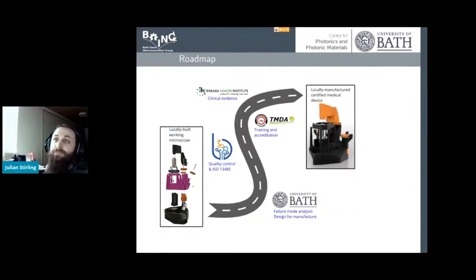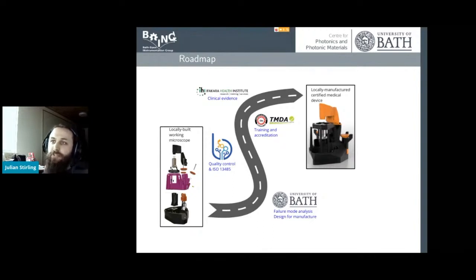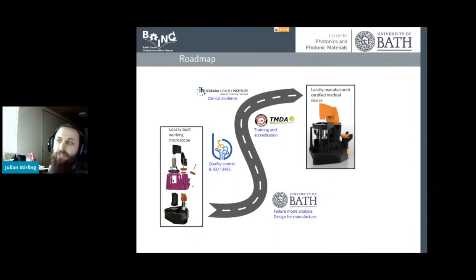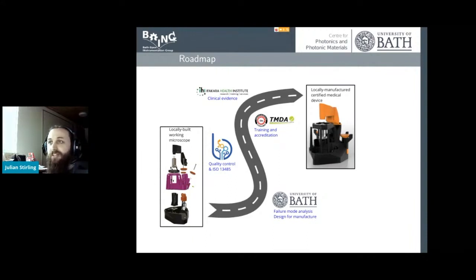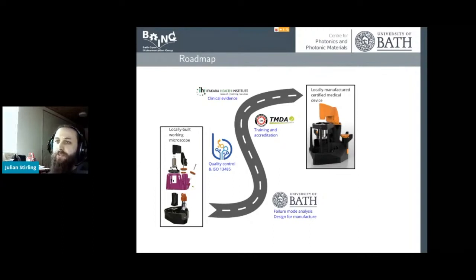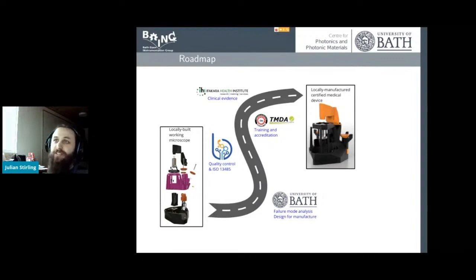In the case of the microscope, I drew out a roadmap: we've got locally built working prototypes. At the university, we need to do failure mode analysis and finalize design for manufacture. Our partners in Tanzania — Bongo Tech and Research — who will be the first producers, need to start building their quality management system up to ISO 13485 for all their production and procurement. Part of that will be getting training and accreditation from the Tanzania Bureau of Standards and Tanzania Medical Devices Authority. It's actually the first in vitro diagnostic device to be made in Tanzania, so this is a learning process for both Bongo Tech and the standards agencies. We also work with Ifakara Health Institute for gathering clinical evidence. The actual final step to get it into a hospital is probably at least as much work again.